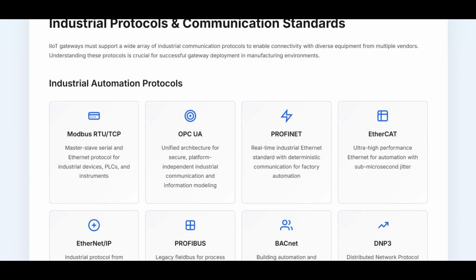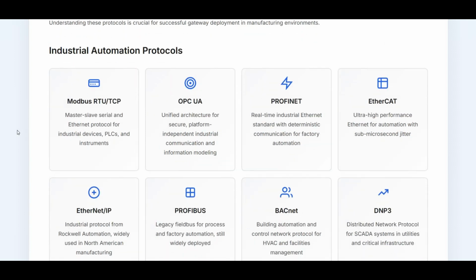Let's talk about protocols, because gateways exist largely to handle protocol diversity. Now, in industrial automation, Modbus RTU and Modbus TCP are everywhere. They use a master-slave model and are simple, reliable, and widely supported. So, OPC UA is different. It's a unified architecture that combines communication with information modeling. Instead of just reading registers, you browse structured data models. It's secure, platform independent, and increasingly common in modern systems.